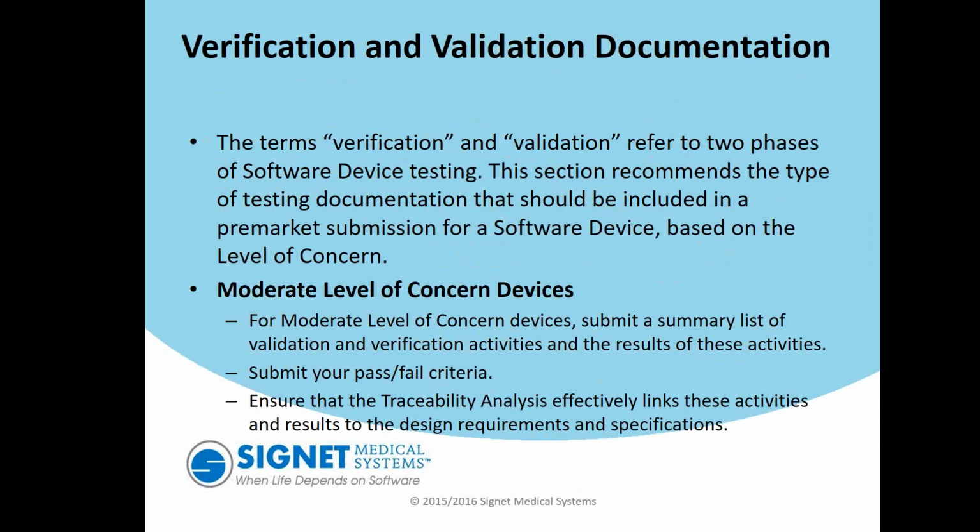But the verification and validation means you have thoroughly tested the entire application for all of its functionality: its reporting functionality, its logging functionality, its error control functionality, its hazard control functionality, its user interface functionality, or device interface functionality if you're working in an environment where your software is providing data to another device. So it is not just testing the algorithm.